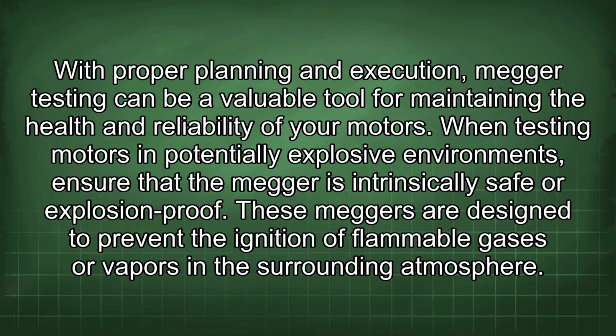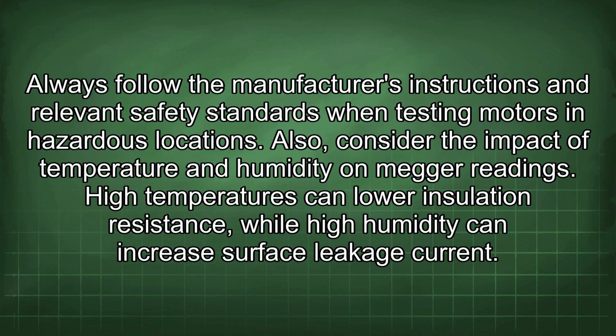When testing motors in potentially explosive environments, ensure that the Megger is intrinsically safe or explosion-proof. These Meggers are designed to prevent the ignition of flammable gases or vapors in the surrounding atmosphere. Always follow the manufacturer's instructions and relevant safety standards when testing motors in hazardous locations.